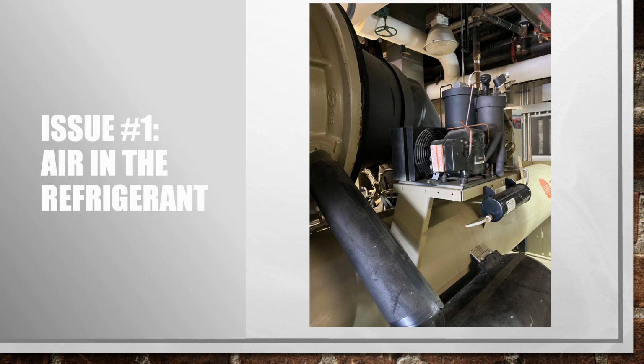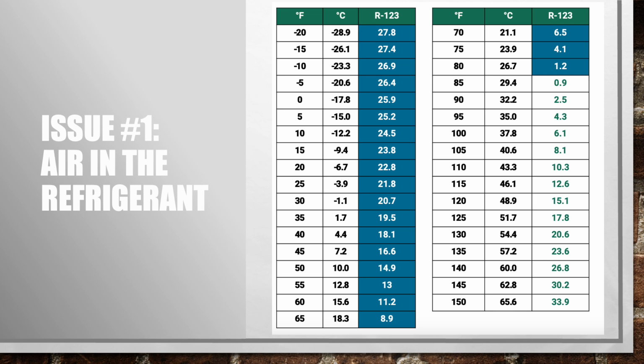If you want to check and see if there's air in the system, it's pretty simple. Just shut everything down, run both your pumps, and then check your pressure and temperature on your pressure temperature chart. So you should have a 0 degree approach if there's no air in the system. If there's air in the system, you might have a couple degrees approach, a couple PSI difference between what it should be and what you're actually reading.